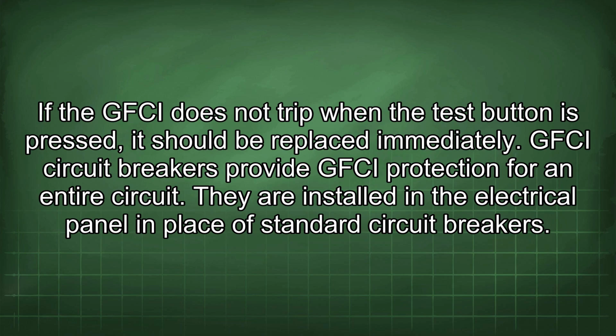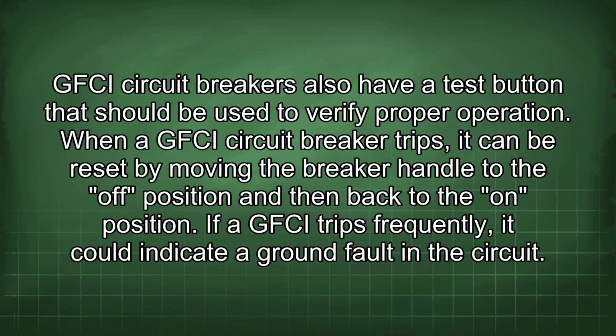GFCI circuit breakers provide GFCI protection for an entire circuit. They are installed in the electrical panel in place of standard circuit breakers. GFCI circuit breakers also have a test button that should be used to verify proper operation. When a GFCI circuit breaker trips, it can be reset by moving the breaker handle to the off position and then back to the on position.